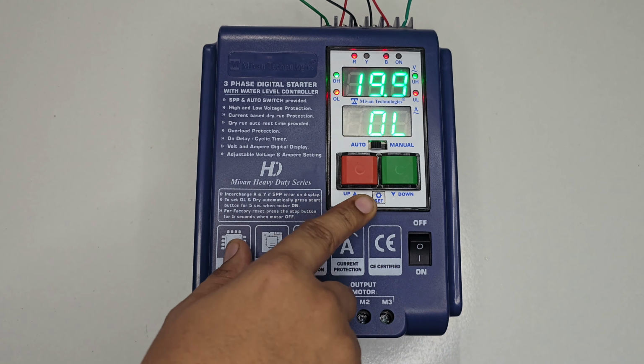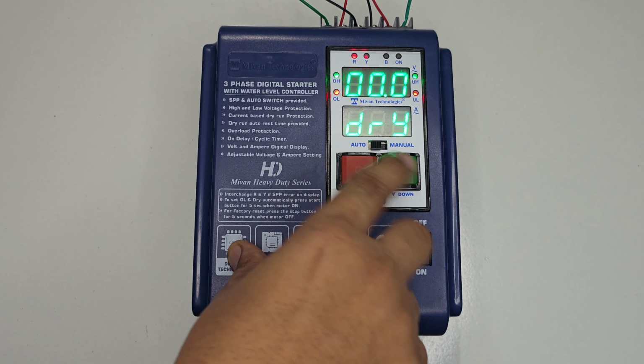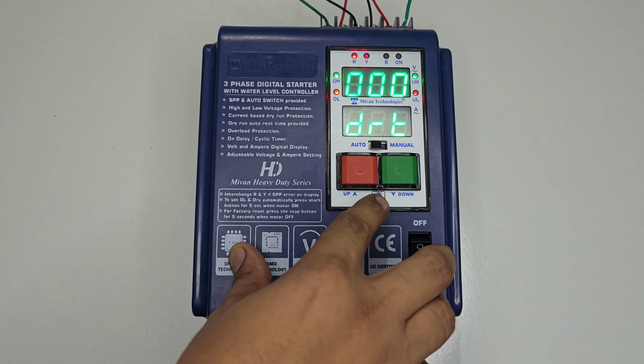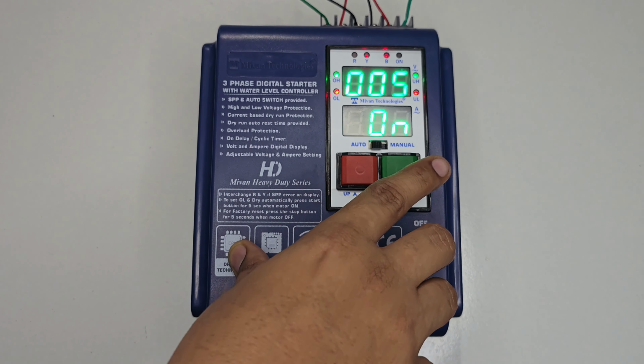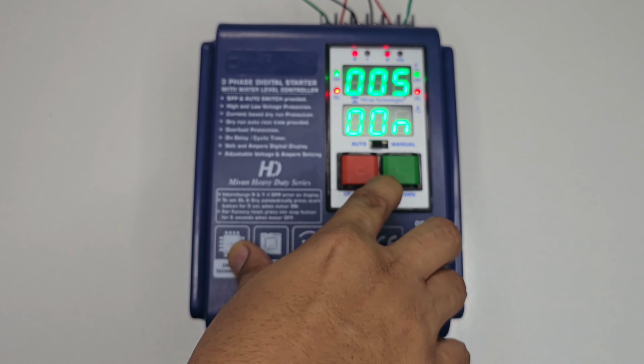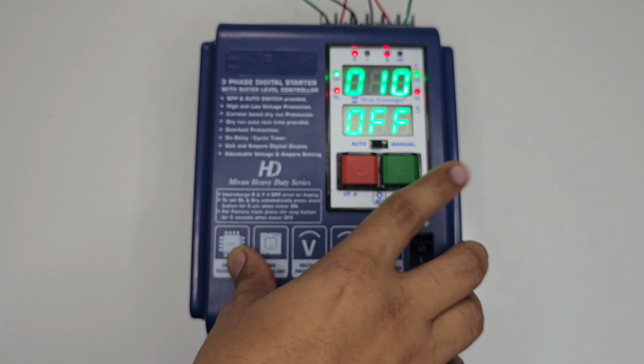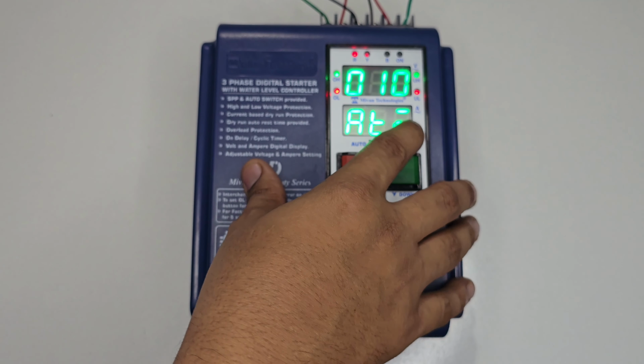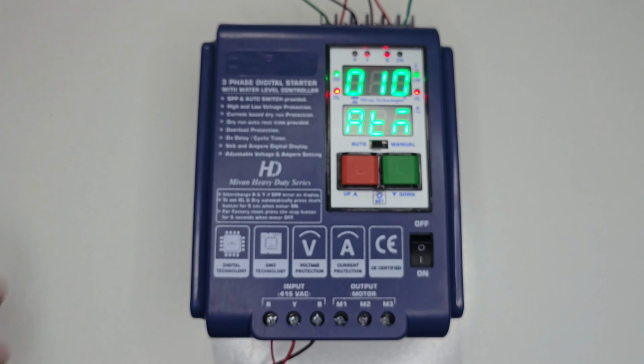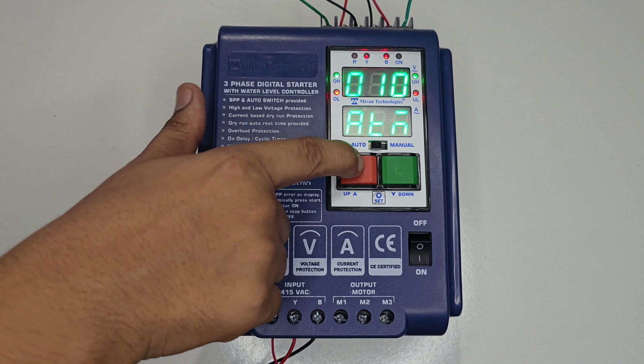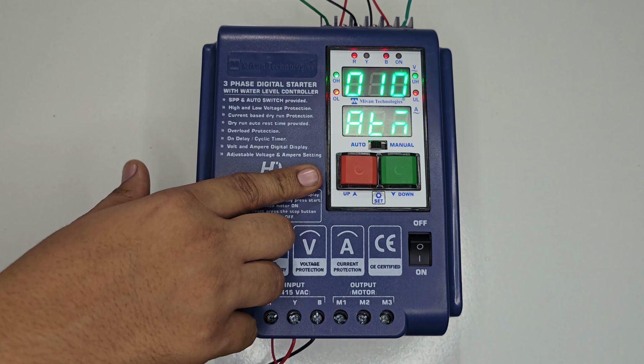Now press the set button, OL comes, set button, dry comes, set button, dry run reset comes, set button, cyclic on mode comes, cyclic off mode comes, and here you can see the on delay time. This time is in seconds. You can adjust the seconds by the up and down key.